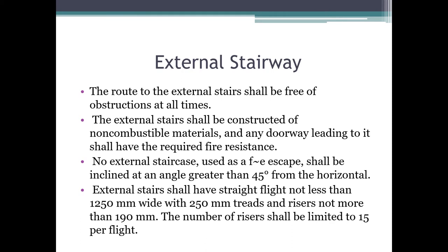Next is the external staircase. You might have seen an external staircase. What is an external staircase? Basically, this is a staircase which is given outside of your building. It is made of non-combustible material. Any doorway leading to the external staircase should be fire resistant for at least 2 hours, so that people on the external staircase can be safe and can evacuate as fast as possible.